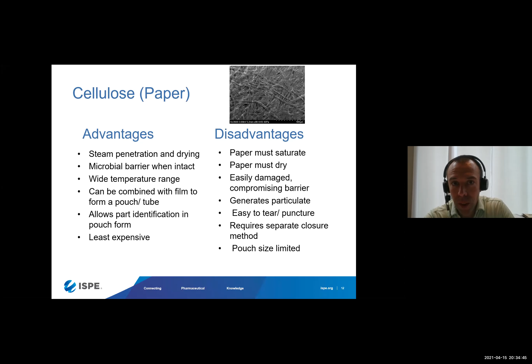So here's another type of paper, the blue wrap, which we saw before. Again, a scanning electron microscope image looks very similar to the kraft paper on the previous slide. Again, you can see the fibers have a pretty tight format there, which does in fact block microorganisms when intact. So the advantages, very similar to the previous slide, with good steam penetration and drying. It is an effective microbial barrier when intact, compatible with a wide temperature range through the sterilization process.